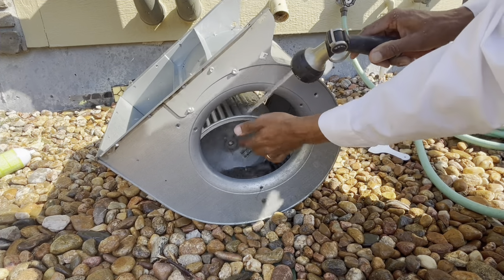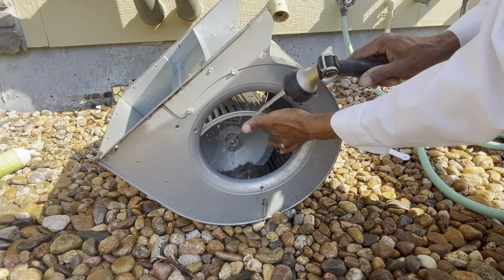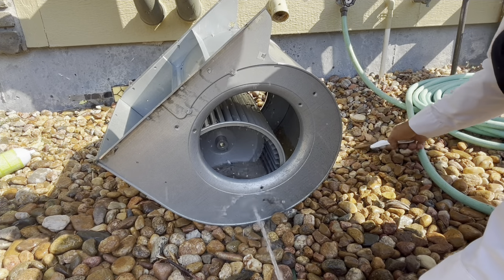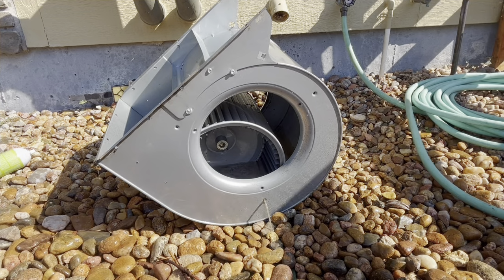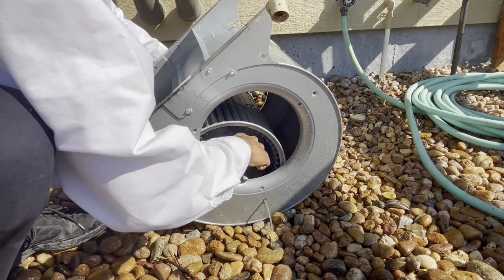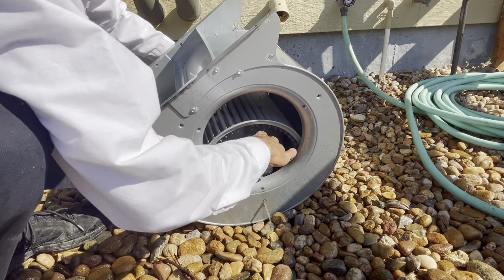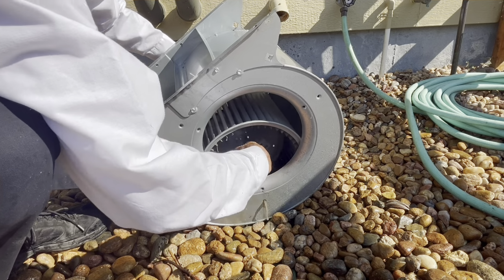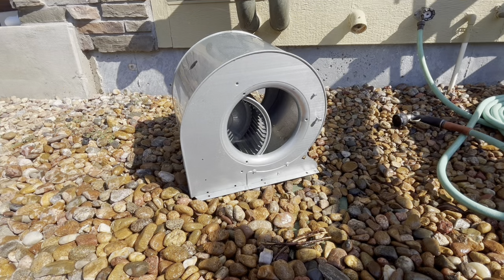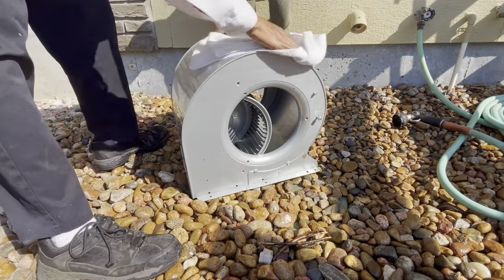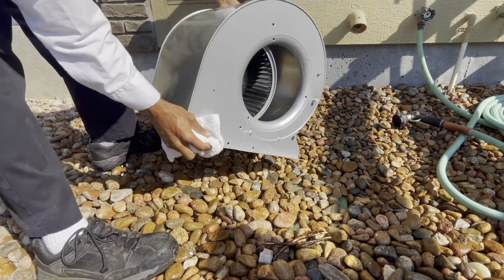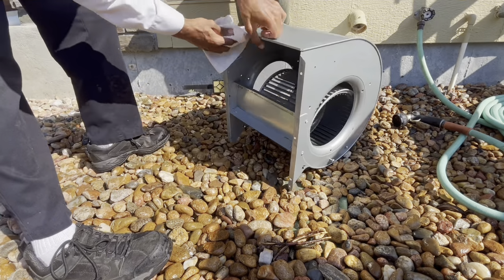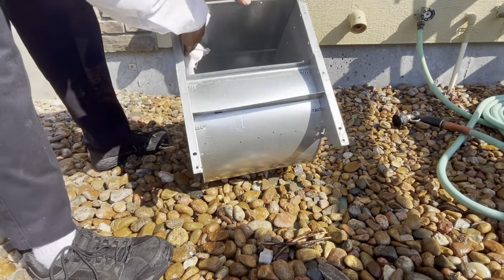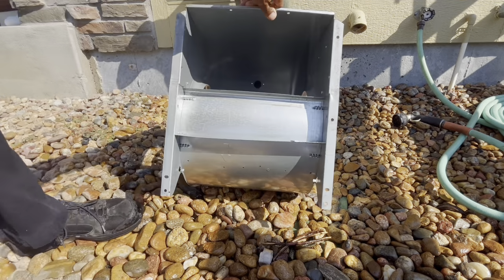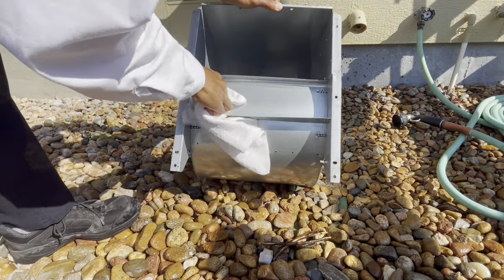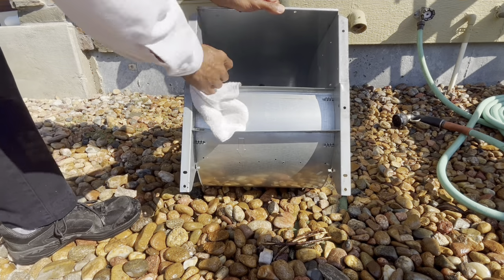So usually I let clients know, when we just stop by the house at the beginning of the conversation, that depending on the condition of the system, it could take 1.5 to 2 hours or longer. It may even take 3 to actually get it as clean as possible. Because I'll take just about every component out besides the heat exchanger, unless we need to verify the operation and condition of that too. But usually you can see it, especially on the Goodman high efficiencies. I don't have a picture right here of it, but you will look at the burners, and you will see rust around the burners on the inside of the furnace.